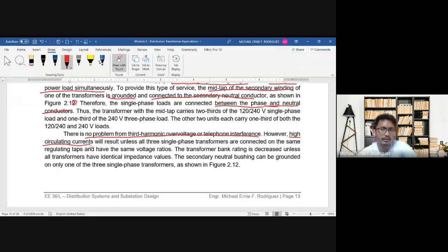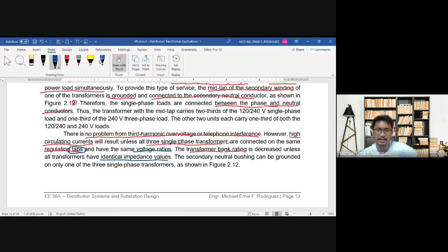Unless the three single-phase transformers are connected on the same regulating taps with the same voltage ratio, the bank rating is decreased, unless all transformers also have identical impedance values. So it's important in banking that the taps, voltage ratio, and impedance values are all the same.